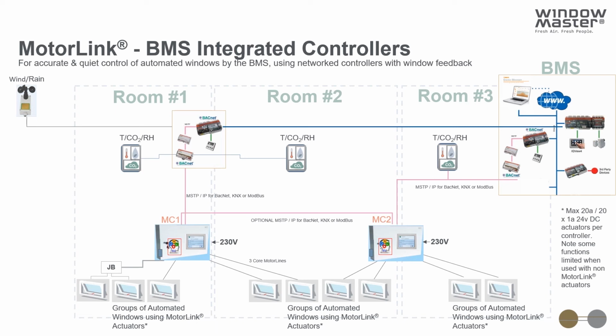Typical system layout for BMS integrated controls, as you can see there, you would have the BMS network with its own wind and weather sensor. You would have temperature and CO2 sensors onto the BMS network, and then you would have the Motorlink controllers stationed at different positions around the building, wired out to groups of actuators, and each group of actuators can be independently controlled even though they're on the same motor controller. The BMS then can communicate through nominated addresses to each of those motor lines to control the groups of actuators to deliver a very high level of control, and very quietly too.